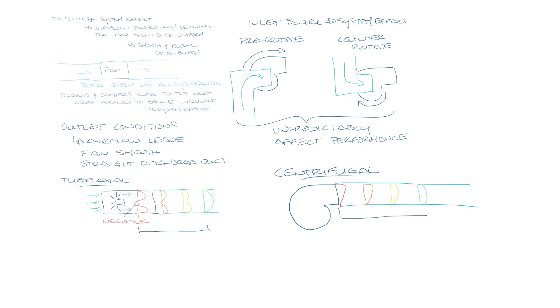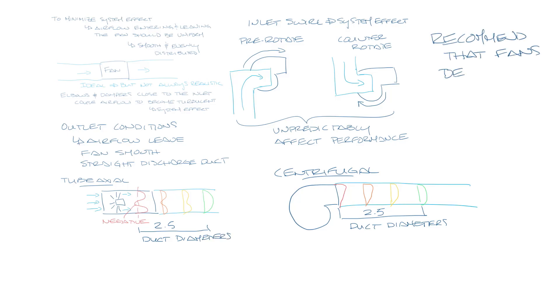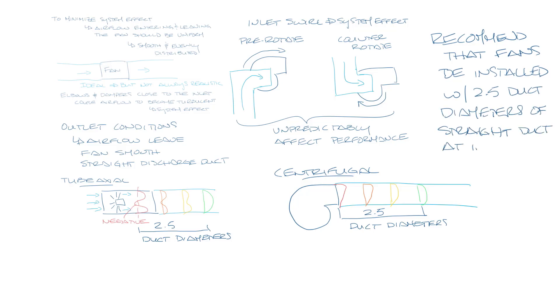It typically takes about two and a half duct diameters for the airflow pattern to smooth out in either one of these cases. Because of this, it's recommended that fans be installed with two and a half duct diameters of straight duct into and out of the fan before any dampers or elbows are installed.